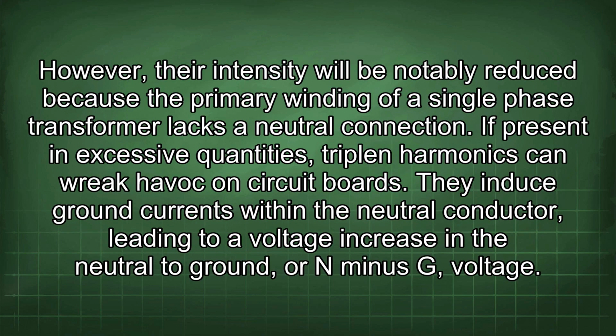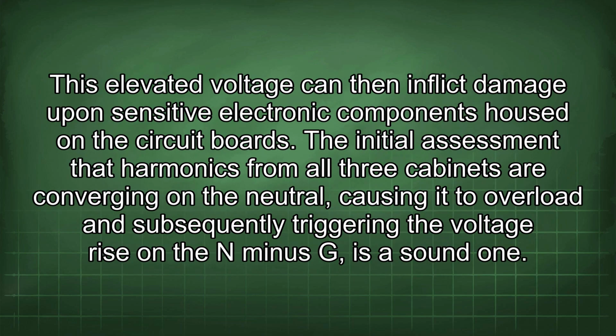However, their intensity will be notably reduced because the primary winding of a single-phase transformer lacks a neutral connection. If present in excessive quantities, triplen harmonics can wreak havoc on circuit boards. They induce ground currents within the neutral conductor, leading to a voltage increase in the neutral to ground, or N-G, voltage. This elevated voltage can then inflict damage upon sensitive electronic components housed in the circuit boards.